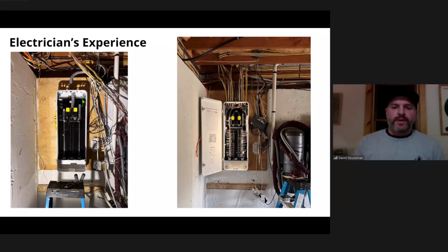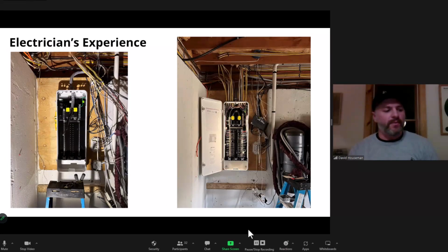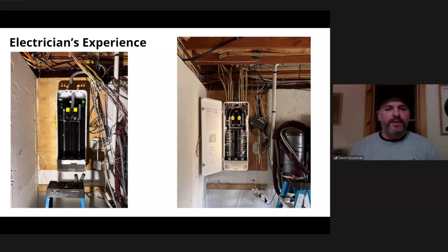As far as the connection, there's a wireless connection point, a hardwired connection point, and also a cellular network that it connects with. But the preferred method is a hardwired Ethernet connection, which should be shielded, because there's a lot of noise inside that panel, so a shielded cable does the job.